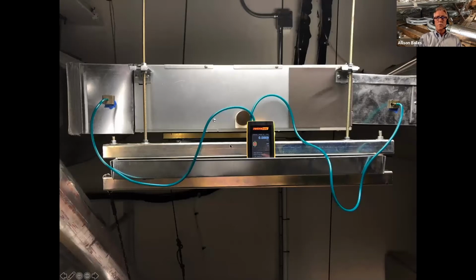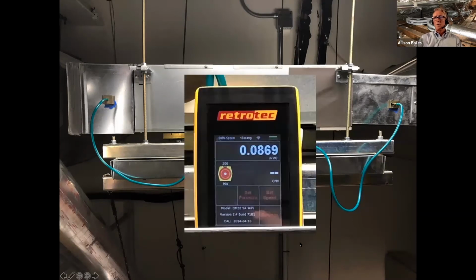And I measured the total external static pressure. That tells you how good it is. And the system is rated for 0.2. It's running at 0.09. So we're only halfway to the pressure that we could have used. So we've got a really good duct system on this. Now this one is pretty short, and I don't have the schematic for this duct system in the presentation, but it is a fairly short duct system compared to the ones at my house.